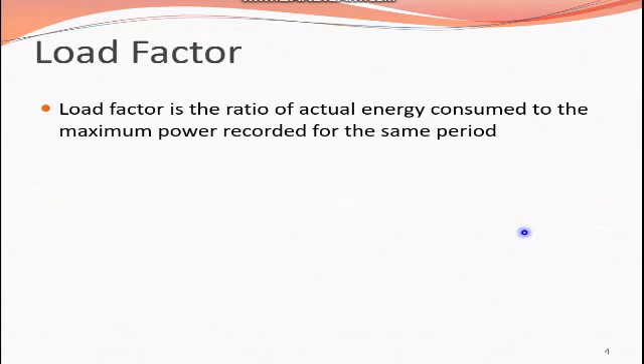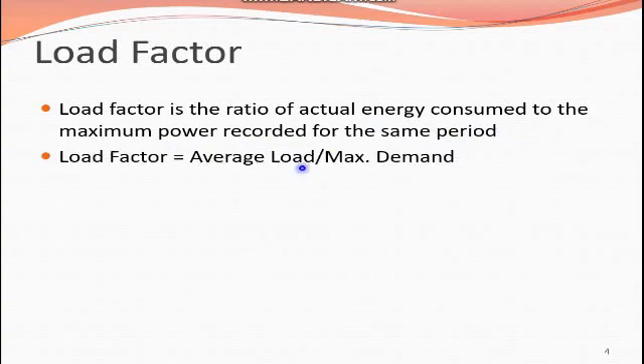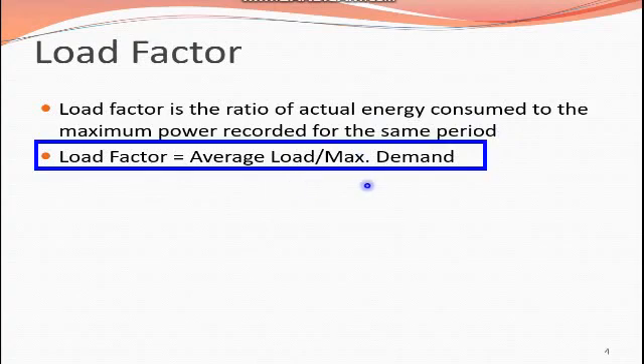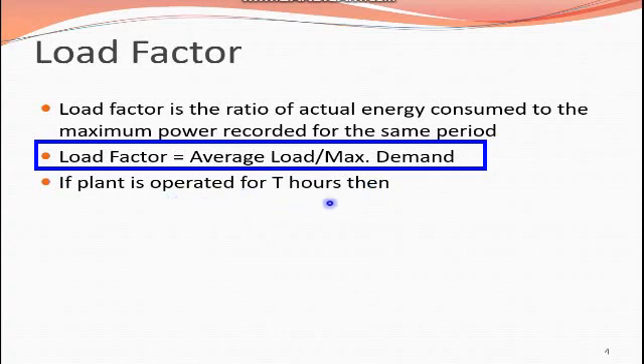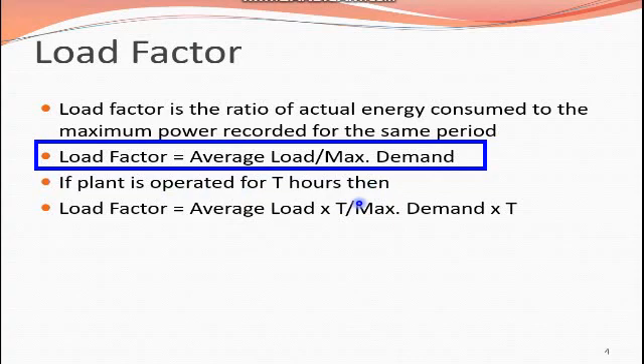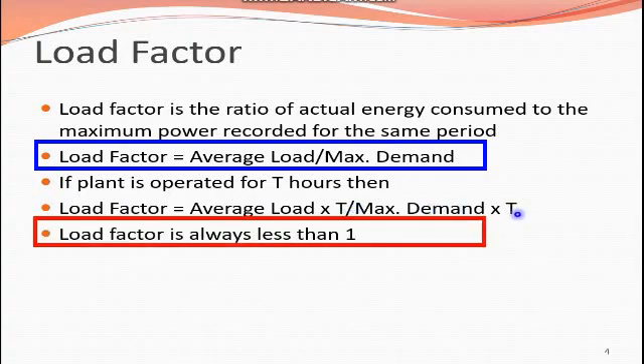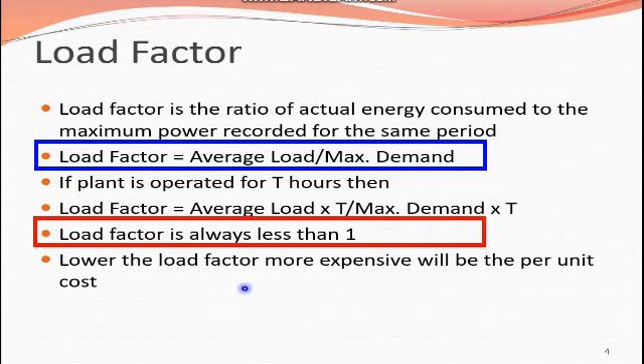Load factor is the ratio of the energy consumed to the maximum power recorded for the same period. Load factor equals average load divided by maximum demand. If the plant is operated for T hours, the formula becomes: average load multiplied by time period, divided by maximum demand multiplied by time period. The load factor is always less than one.